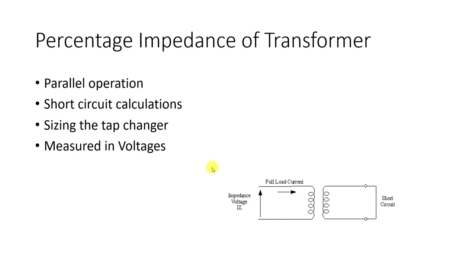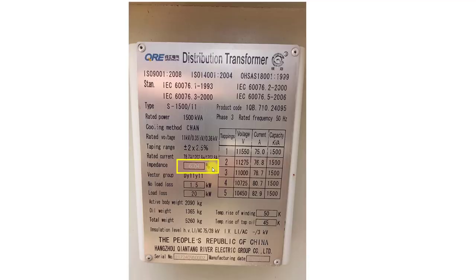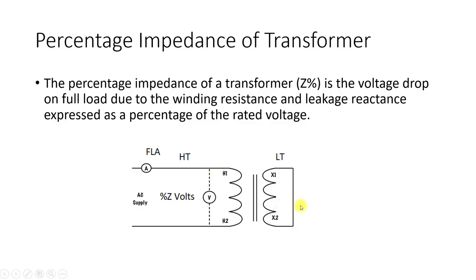The percentage impedance is measured in voltages. The measurement procedure is very interesting and has been tested in the lab. To measure the percentage impedance, you first short-circuit the low-voltage side. Make sure the shorting conductor can carry the full load current of the LV side — calculate the full load current, take a 10–20% margin, and then short the LV winding.